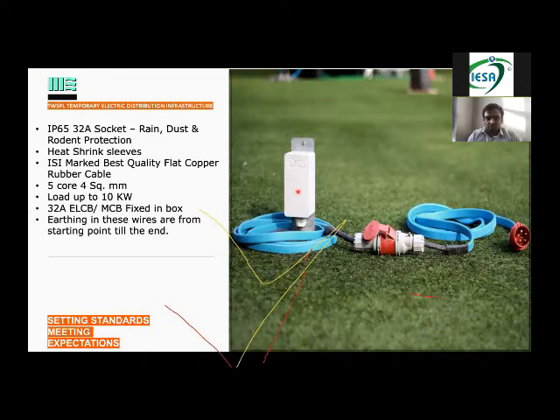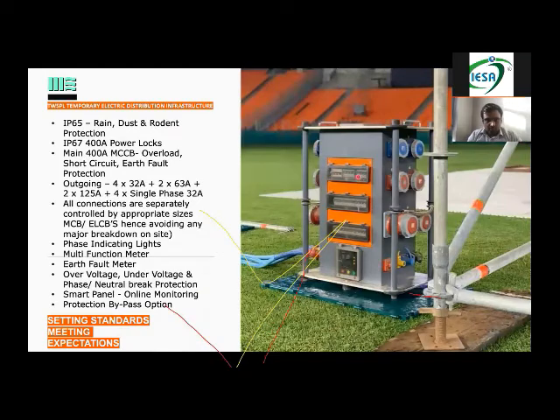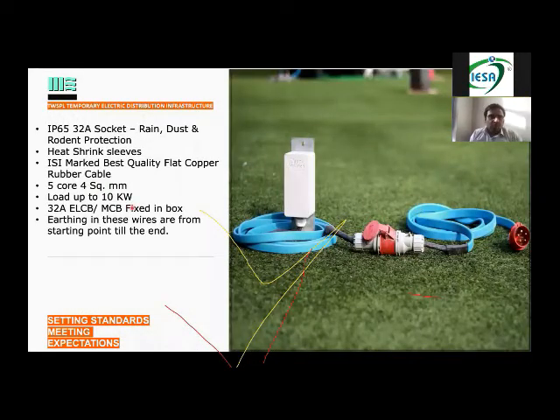Now, just to give you an example, if you try to break any chain, basically inside this there is a 32 amp socket. This is also a 32 amp MCB. This is a socket. The cable is 4 mm. The MCB inside is 32 amp, and the socket is also 32. If now I try to play a little bit and undersize my cable, maybe I'm not using a 4, I start using a 2.5. What will happen? The load will come according to 10 kilowatts. The wire will start getting heated up. In this case, we have an MCB, so it will trip because of the overload.